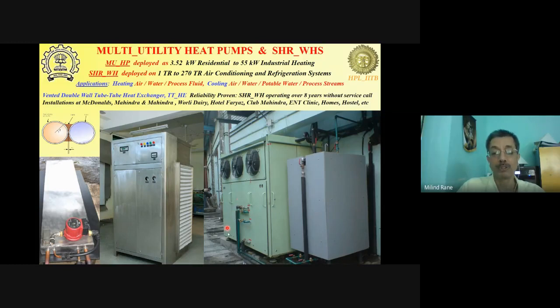It also produces chilled water for drinking, or for the water which is carbonated and served as Coke and other cold drinks and things like that, being pre-cooled from 32 degrees to 12 to 15 degrees centigrade using the same unit. And so 3 utilities were being served: DX cooling in the kitchen, hot water for sanitation, and chilled water for dispensing as soft drinks and for drinking purposes.